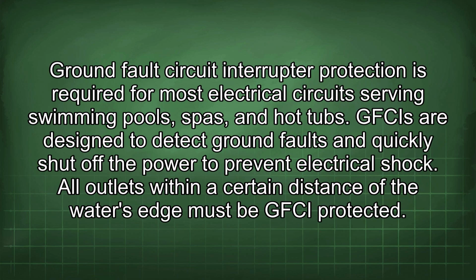Fourthly, GFCI protection. Ground fault circuit interrupter protection is required for most electrical circuits serving swimming pools, spas, and hot tubs. GFCIs are designed to detect ground faults and quickly shut off the power to prevent electrical shock. All outlets within a certain distance of the water's edge must be GFCI protected.